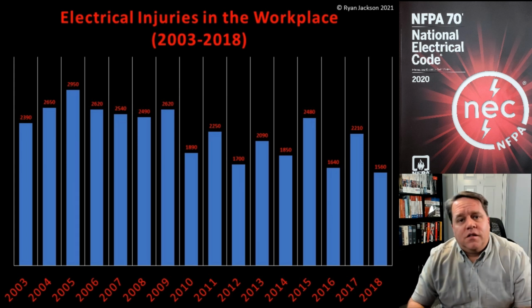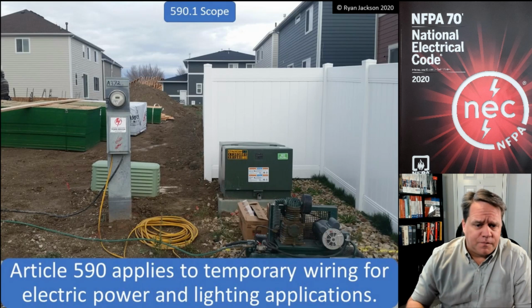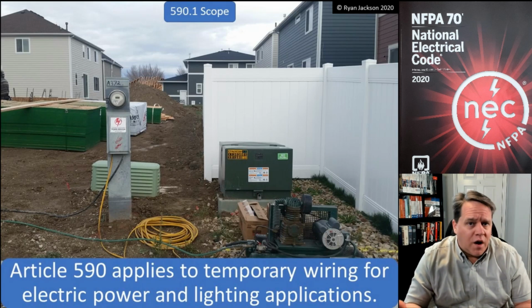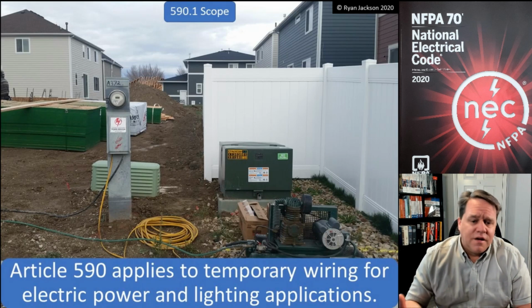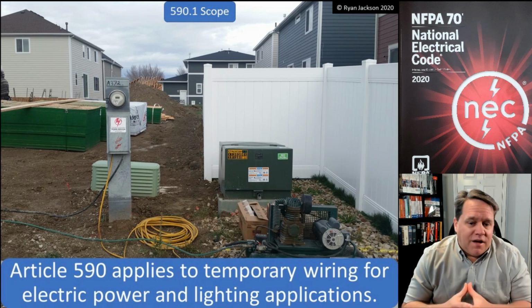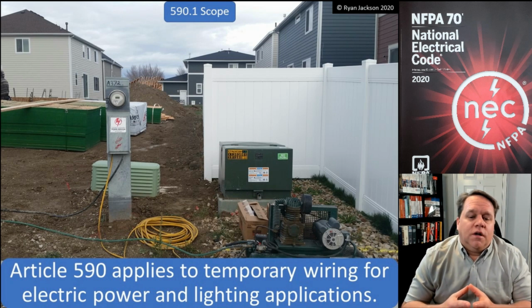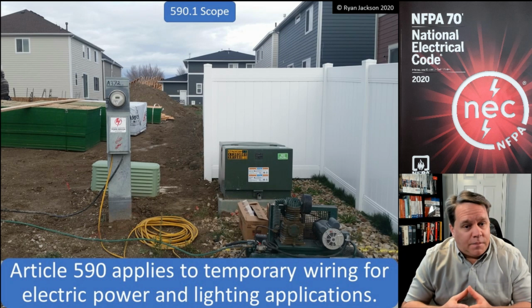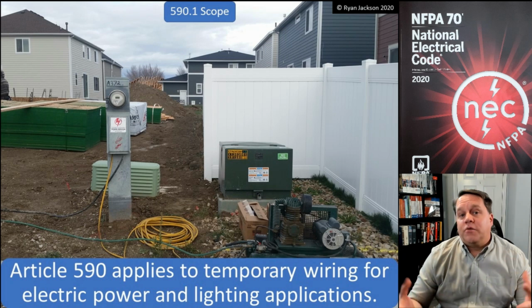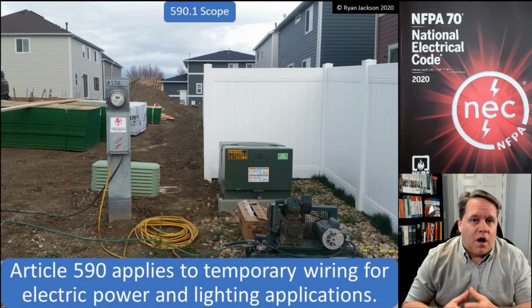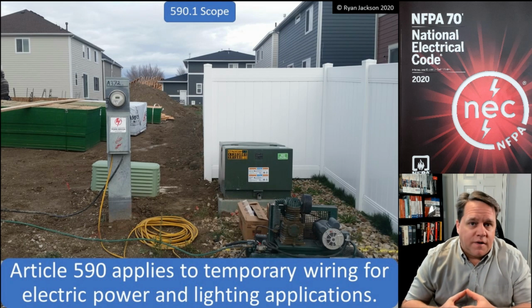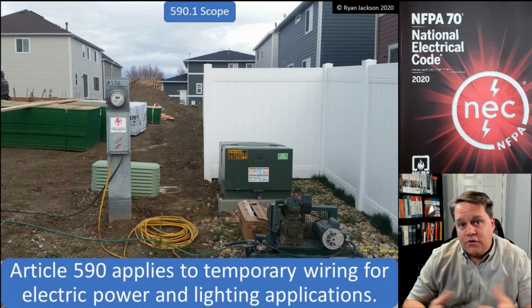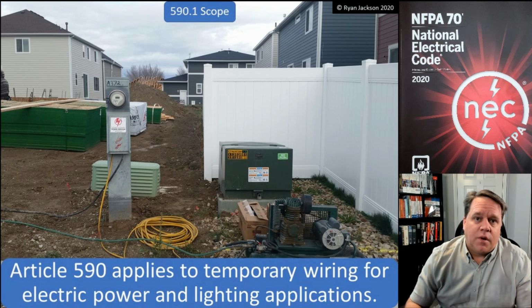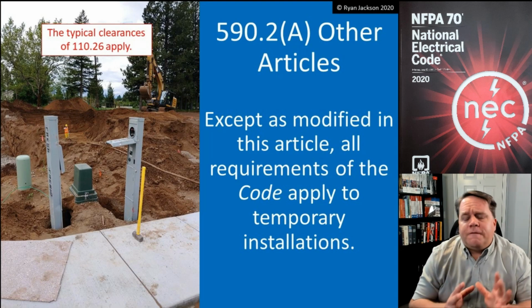All right, let's get into the technical side and talk about some of the rules. When we get into temporary wiring, of course, we're talking about Article 590. Article 590 applies to temporary wiring for electric power and lighting applications. All right, so a job site is probably the most common application for Article 590, although it's not necessarily limited to construction sites, but that's probably the most common use.